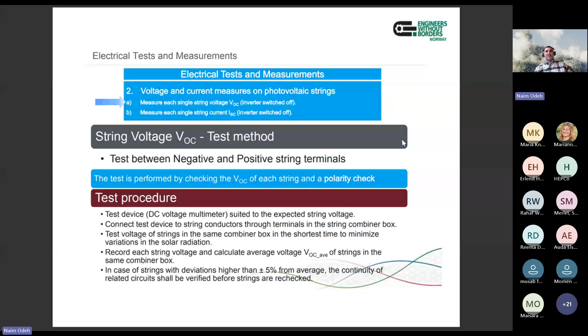So you check for string 1, string 2, string 3, and take the records. If the differences are within plus or minus 5%, that means they are okay. If the voltage for any of the strings is out of this range compared with other strings, you need to investigate the situation of that string. Check the modules, check the connections, check the MC4 connectors, and find out why the voltage there is different from others.